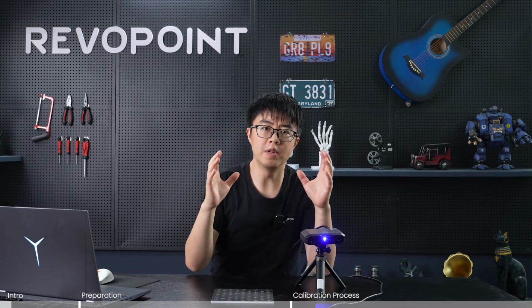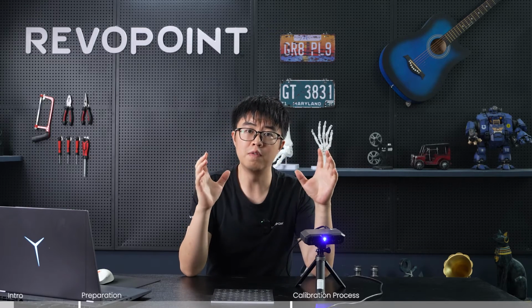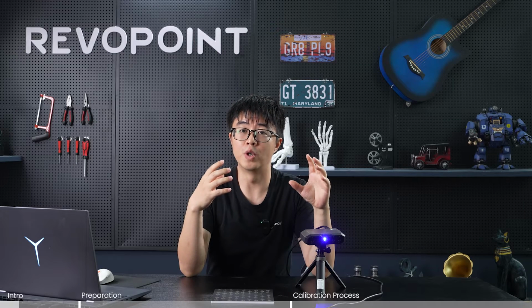One last thing you should know about your MINI scanner. Now let me tell you how to do the calibration. Keep this in mind: once you receive your MINI scanner, we have done the calibration for you in the factory, but because you might have bought your MINI scanner after a while, and especially after we have updated our firmware, it's better to recalibrate your MINI scanner once you receive it for better performance.